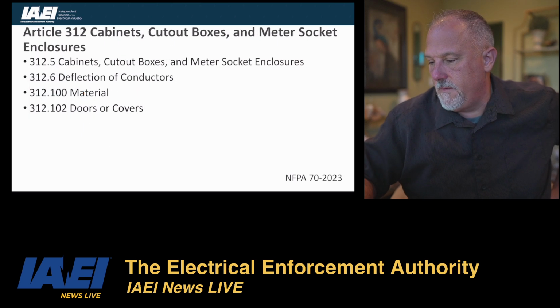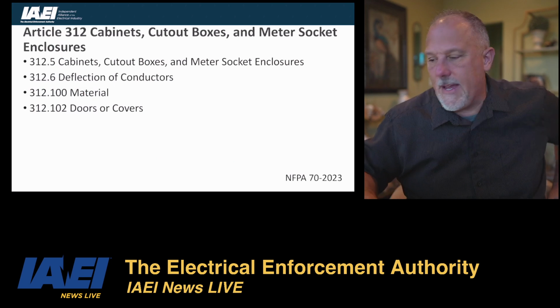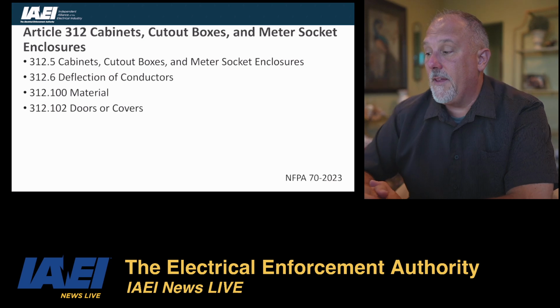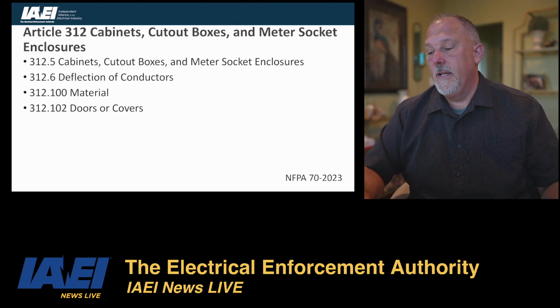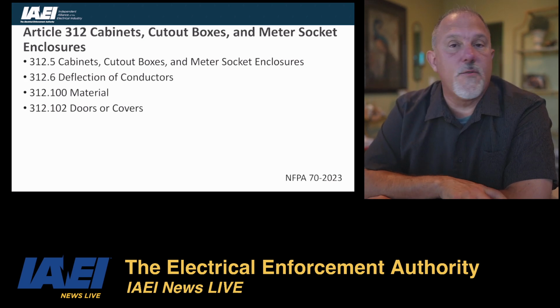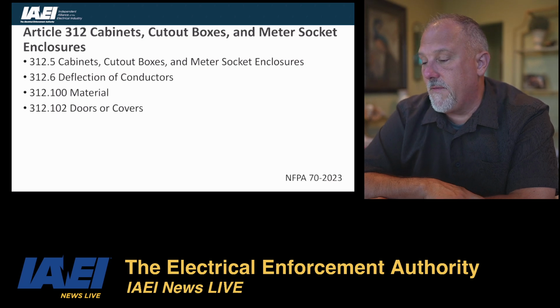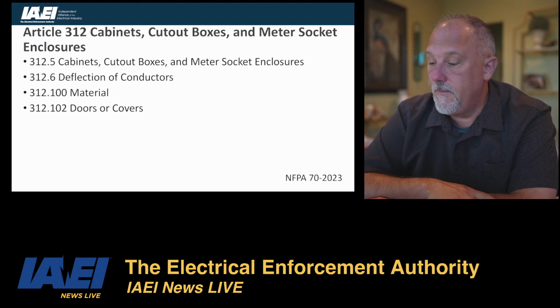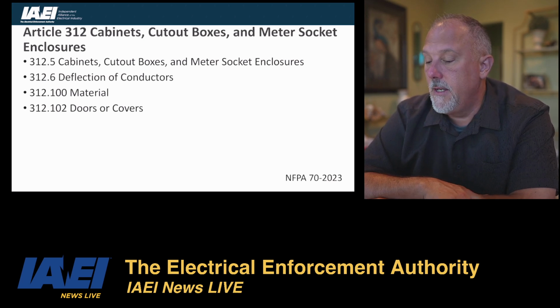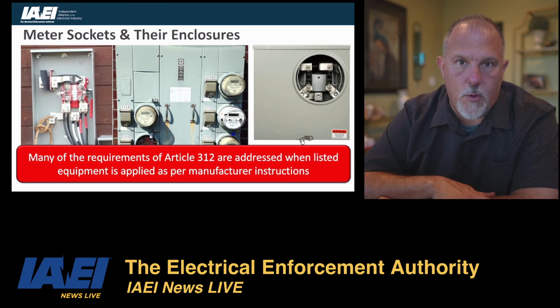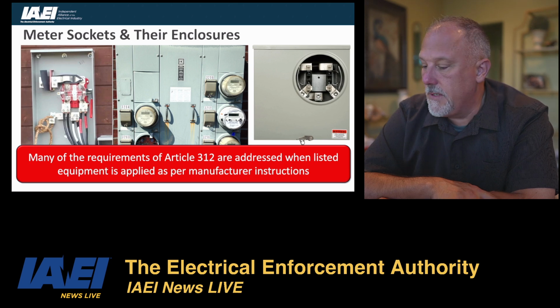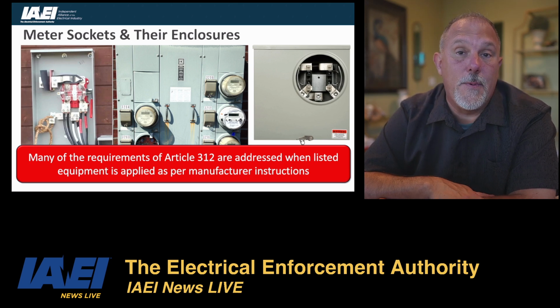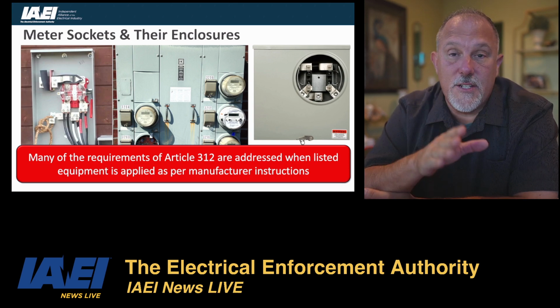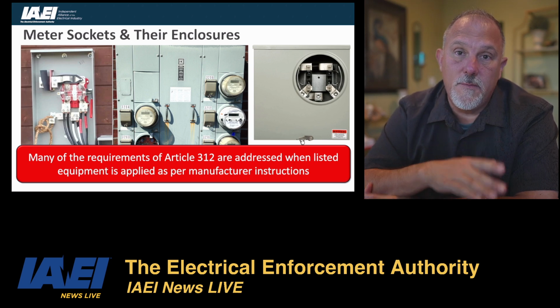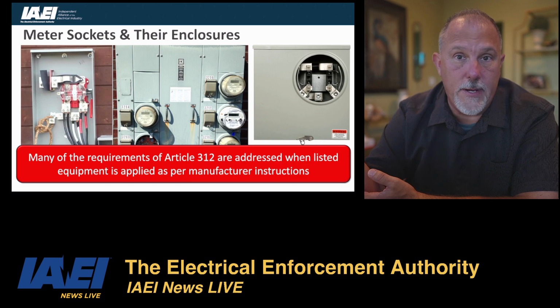Let's take a look at 312. In 312, you have to think about cabinets, cutout boxes, and meter socket enclosures. They specifically call out meter socket enclosures. The sections that I could find that directly mention meter sockets are 312.5, 312.6, deflection of conductors, 312.100, and 312.102. Now, I would argue that many of the requirements in Article 312 are addressed when you get listed equipment. Remember, if it's not listed and it's owned by the utility, none of these requirements apply to it anyway.